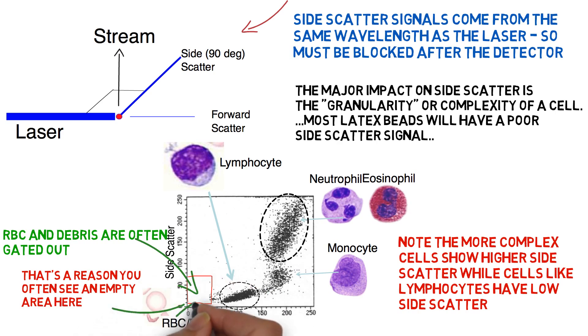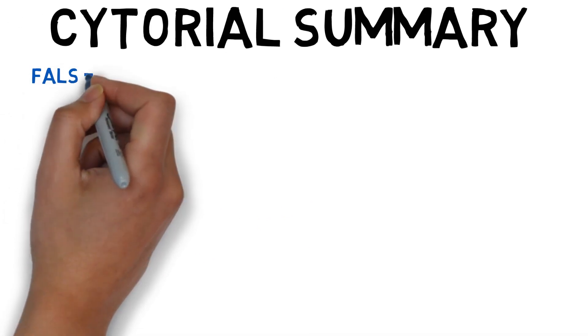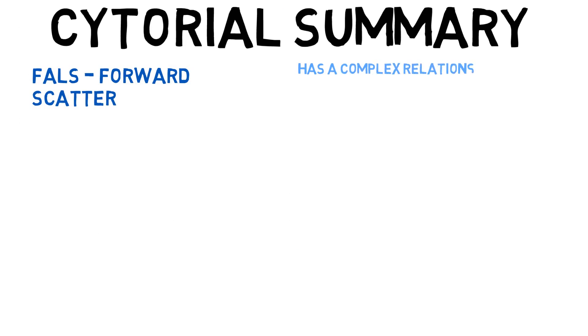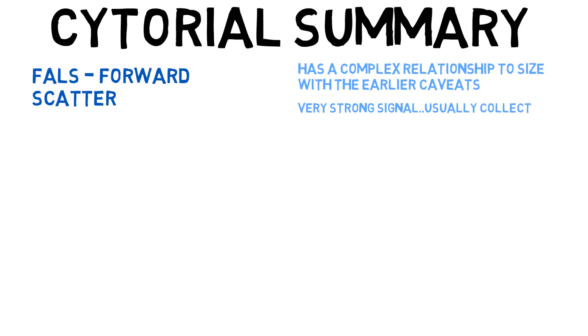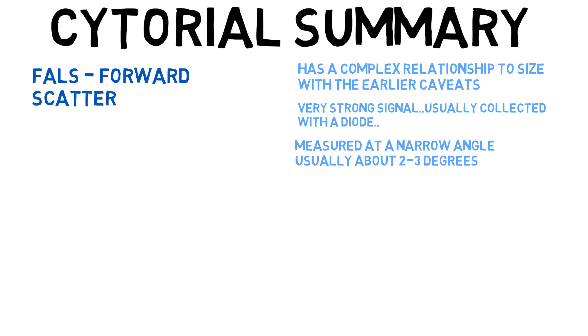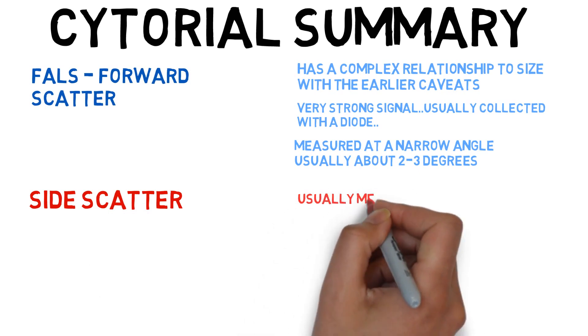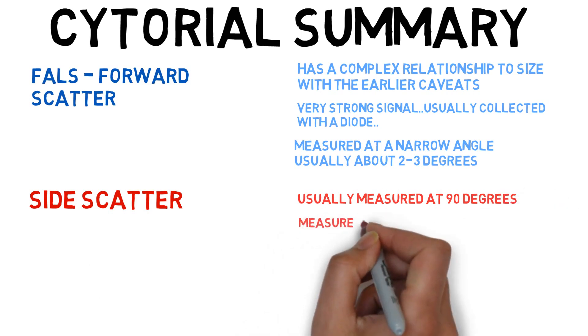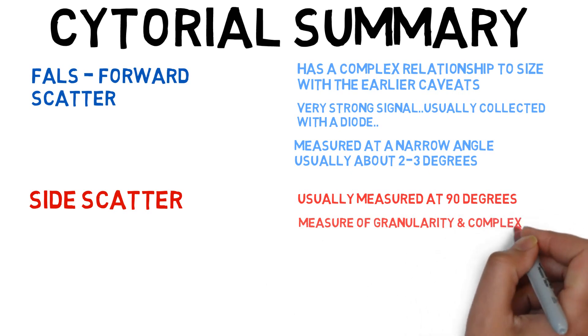In summary, here are our findings on light scatter. For forward scatter — also called FALS and narrow angle scatter — we've identified a complex relationship between size and scatter, with the caveat that non-spherical cells should not be considered linear with respect to forward angle scatter. Since the signal is strong, we can measure it with a low-cost diode, and we mostly measure FALS at about 2 to 3 degrees. Regarding side scatter, that is usually measured at 90 degrees to the laser beam, also called orthogonal scatter or wide angle scatter. It is a measure of granularity and complexity, and combined with forward angle scatter it can be very useful in differentiating several different cell populations.